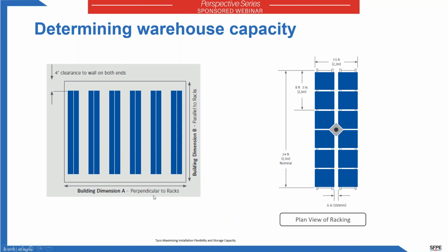So in the figure that you see here on the left, I have a plan view of a warehouse space. And this warehouse space has this bottom dimension, what I call building dimension A, which is perpendicular to the racks, and dimension B, which is parallel to the racks. So assuming that dimension A and dimension B is the available space within a warehouse that you could put all your storage, my analysis is focusing on that area. And I made an assumption that, within this space, there's going to be at least a 4-foot clearance between the racks and whatever is beyond, whether it's a wall or the space that's not occupying. But you're going to have a 4-foot clearance.